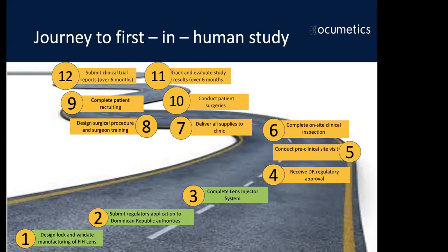Steps 1 and 2. Step 1 is our design freeze. Anytime you go into a study, particularly one that has the regulatory burden that an FDA study would have, you have to stop designing your technology and freeze that design. Well, we have a couple more measurements left to do, and we will be freezing not only one design, but a second design, so that we have two different designs that we can look at as we go into our first in human and the multi-center clinical trial.